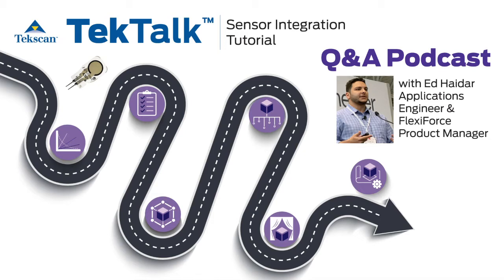Now, if you're going to be living in the neighborhood of that 1.5 volt reference voltage area, we've seen sensors last upwards of 3 million and even more actuations without showing any signs of degradation or loss in sensitivity. So a DC voltage is fine if you're going to be able to power the sensor or supply a reference voltage to the sensor on that 1.5 volt order.